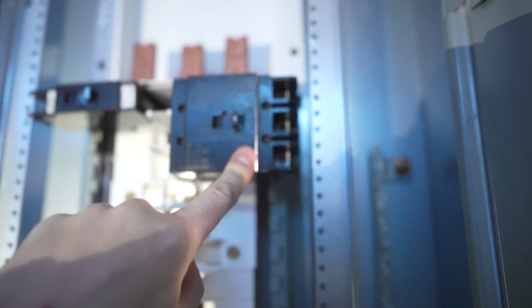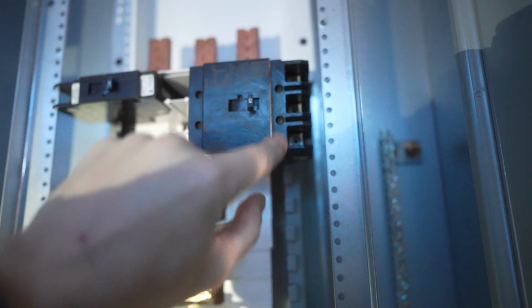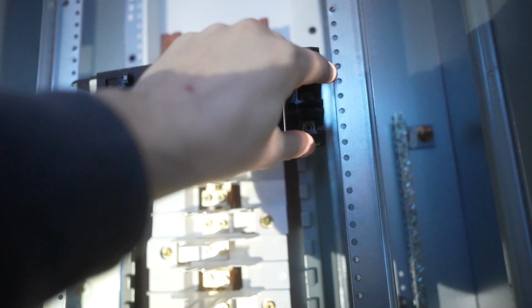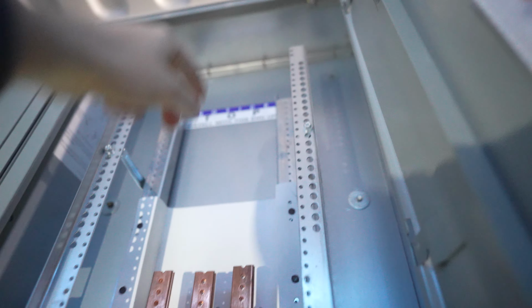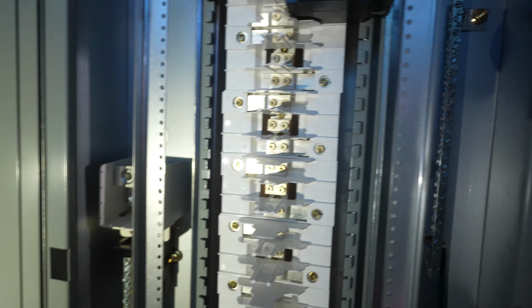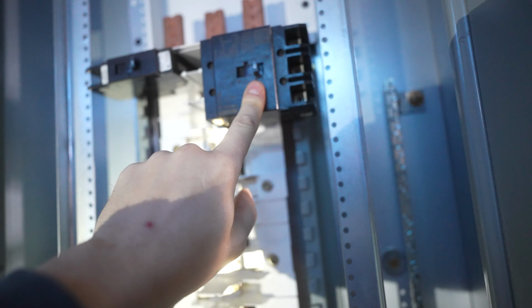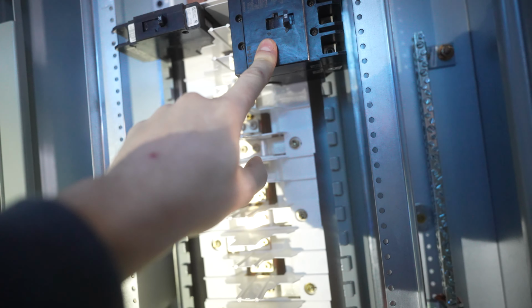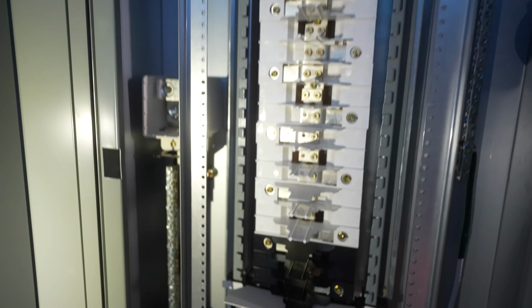For the miners, we're going to be running 6-gauge wire, each leg coming off going to the top there. We'll drill holes through the panel, bring the copper out at the top, drag it along the top, then go down to our racks where it plugs into a PDU. Each one of these is going to run a PDU, so I have one PDU that's 35,000 watts, a second one, and so on. You just load up this panel until the whole thing is full and you're using all the watts available, and we'll do that for all the panels.